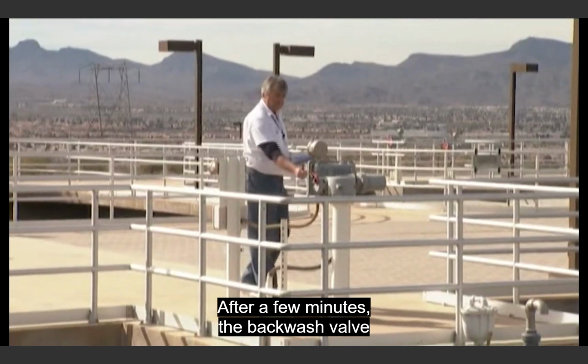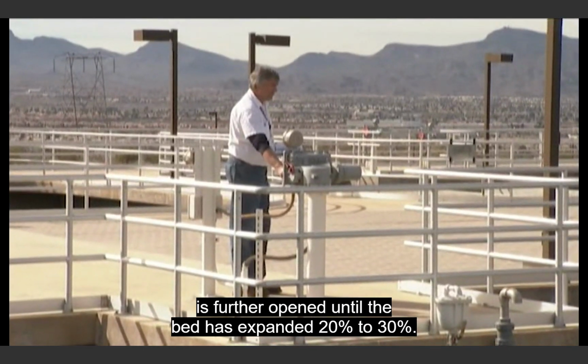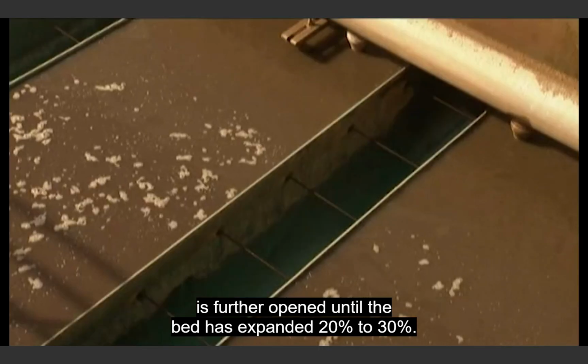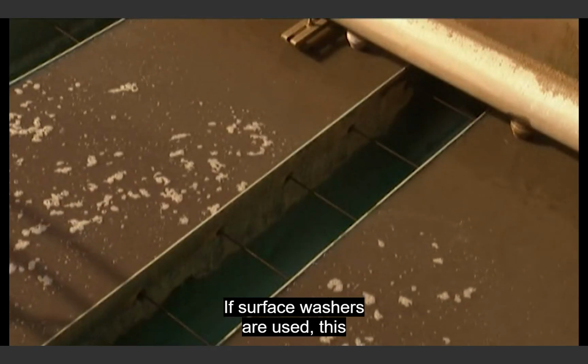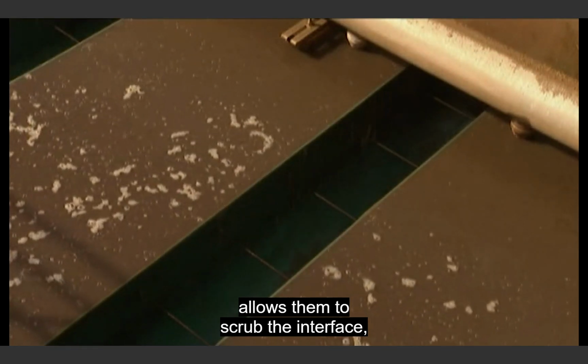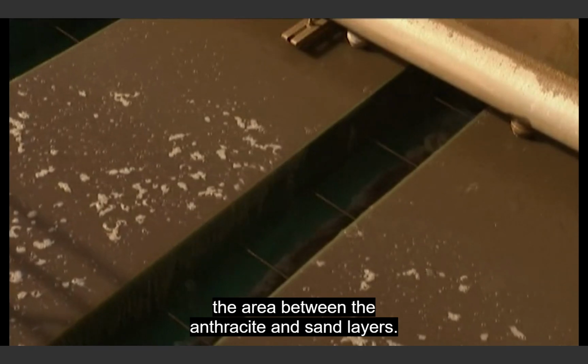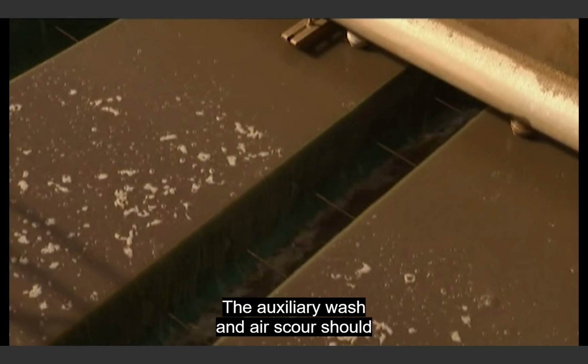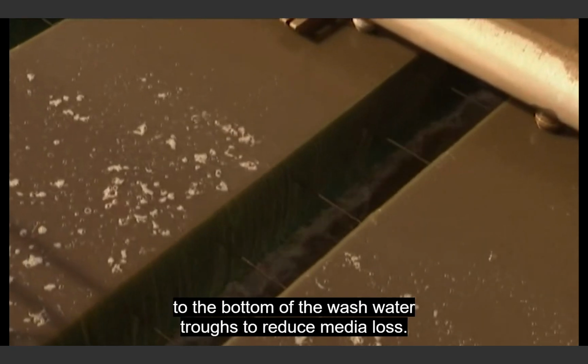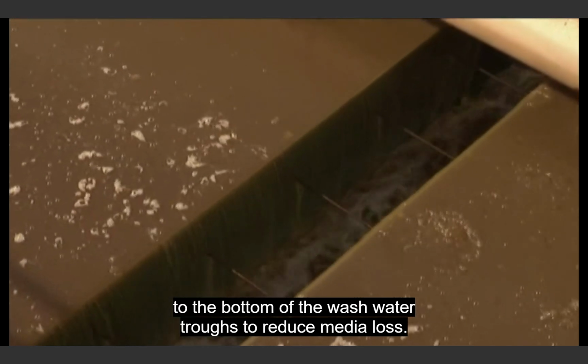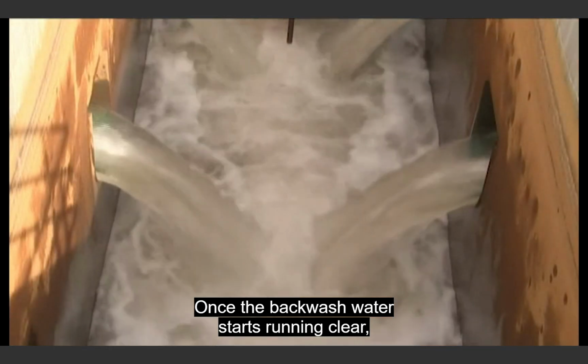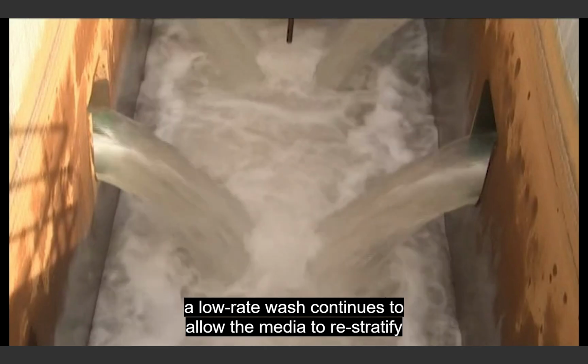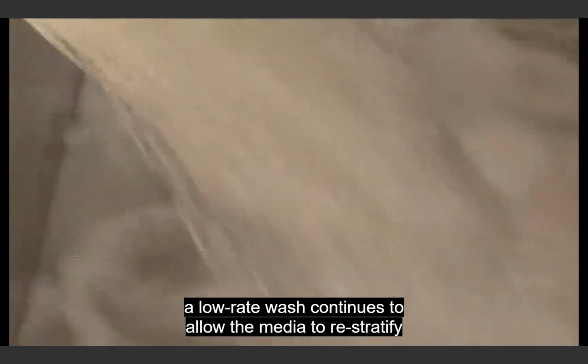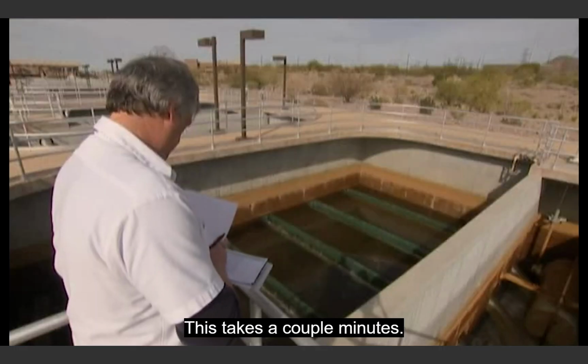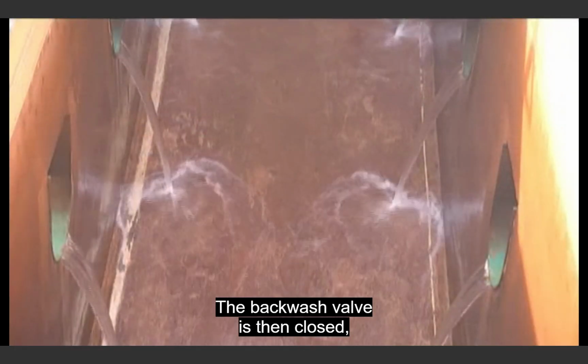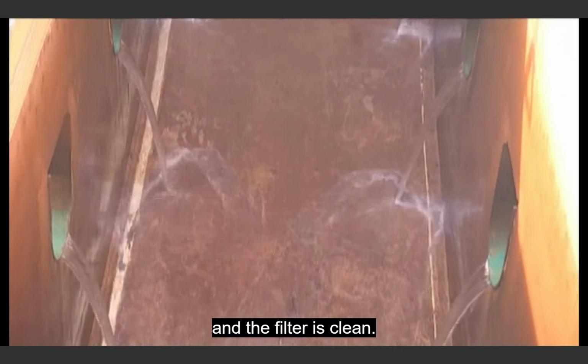After a few minutes, the backwash valve is further opened until the bed has expanded 20 to 30%. If surface washers are used, this allows them to scrub the interface, the area between the anthracite and sand layers. The auxiliary wash and air scour should be stopped before the water rises to the bottom of the wash water troughs to reduce media loss. Once the backwash water starts running clear, a low-rate wash continues to allow the media to re-stratify into layers. This takes a couple minutes. The backwash valve is then closed and the filter is clean.